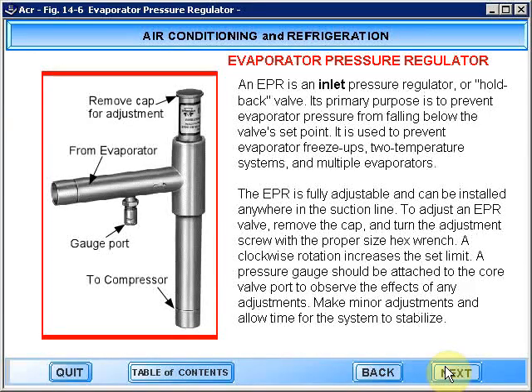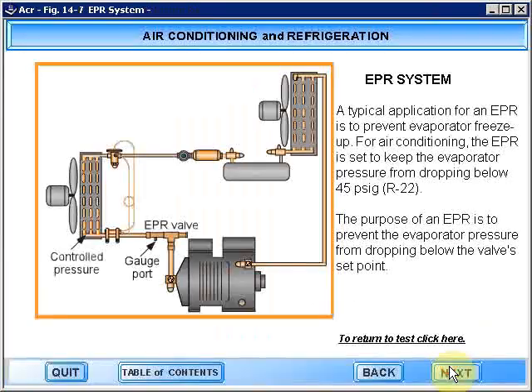To adjust an EPR valve, remove the cap and turn the adjustment screw with the proper size hex wrench. A clockwise rotation increases the set limit. A pressure gauge should be attached to the core valve port to observe the effects of any adjustments. Make minor adjustments and allow time for the system to stabilize.